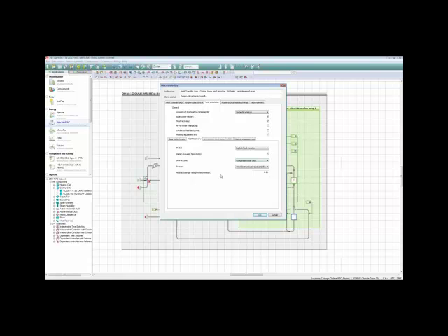And as I described before, this model basically gives you two data points. So I'd specify the delta T at two different data points for the thermal lift between the two loops, and then specify the COP at those two thermal lift data points.